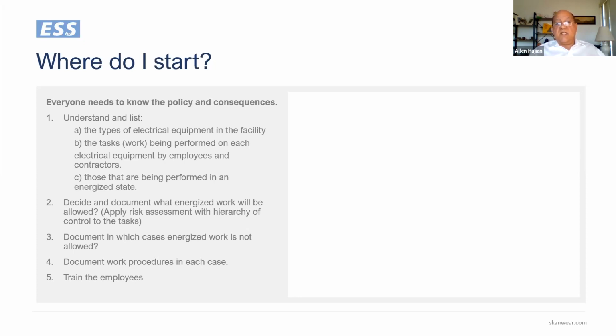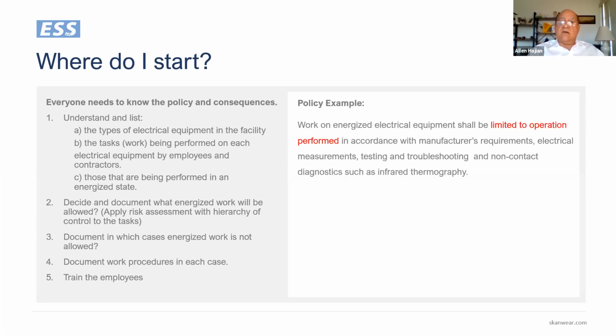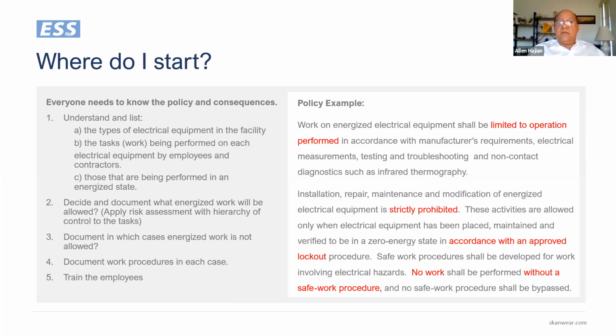So when you are applying risk assessment and hierarchy of control and deciding what energized work is allowed and not allowed, keep in mind the local regulation. For example, Occupational Safety and Health Administration says in US that all electrical equipment have to be placed in electrically safe condition before you work on or near them. And it has some exceptions. So NFPA does too, and we'll talk about those in just a second. So when you write a policy, you want to say, okay, what operations are allowed, limited to operations performed, and what are prohibited. And if they're prohibited, you still have to do the work. You still have to do maintenance, you have to do repairs. So how do you do it? What is the procedure and what is the consequence? So no work without a safe work procedure and no safe work practice shall be bypassed. That's an example of a policy, very short, 2 paragraphs.